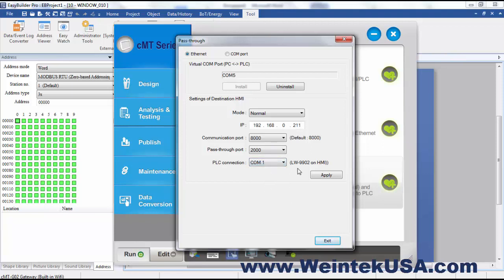And then you can enable your pass-through for COM port. Actually I do not have a serial device set up here at the time, but this is how you would enable a serial pass-through and you would be able to get online with your native PLC software. You would be able to get online over your network through the HMI to your serial connection.